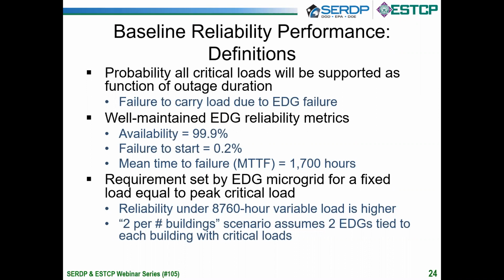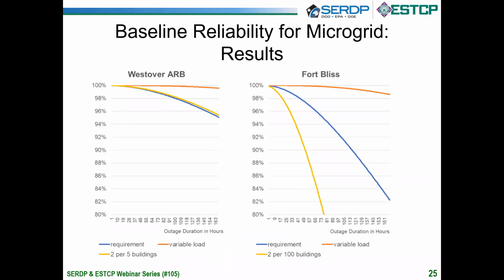So let me first, in slide 25, walk through some of these results. I'm just showing it for the largest and smallest base, Fort Bliss on the right and Westover. So what's plotted here on the y-axis is the probability that this microgrid or backup generator system will be able to supply sufficient energy to support 100% of the critical load. This is plotted as a function of the duration of the outage. Remember, the outage can start at any time during the year, and that is one of the things that contributes to the probability distribution function.